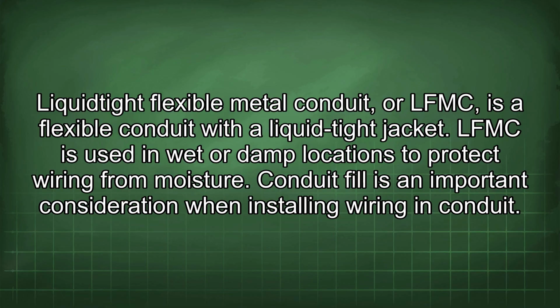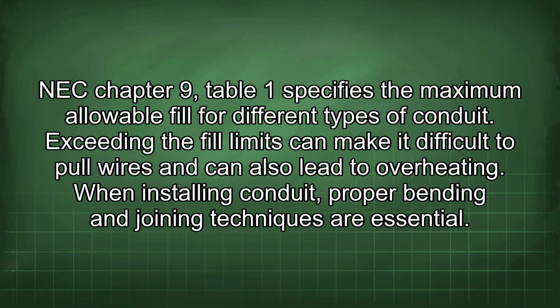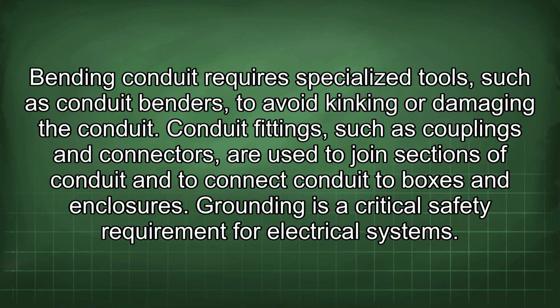Conduit fill is an important consideration when installing wiring in conduit. NEC Chapter 9 Table 1 specifies the maximum allowable fill for different types of conduit. Exceeding the fill limits can make it difficult to pull wires and can also lead to overheating. When installing conduit, proper bending and joining techniques are essential. Bending conduit requires specialized tools, such as conduit benders, to avoid kinking or damaging the conduit.